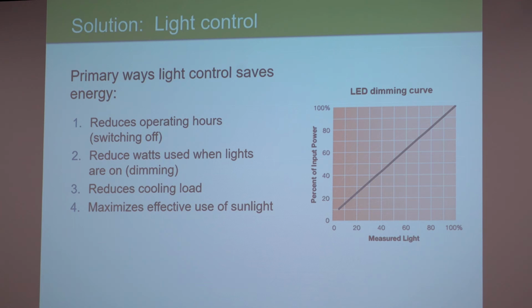Thirdly, light control saves energy by reducing cooling load. Why do you guys think that is? Any ideas? Why does light control reduce cooling load? That's right. When you reduce lighting in the space, there's less heat coming into the space, therefore you don't need to cool the space as much. The rule of thumb is for every 3 watts you save on lighting load, you save about 1 watt in cooling load. That varies by a lot of factors. Geography is a very important factor there, and the more south you are in the country, the bigger that savings is, and the more cooling they use.